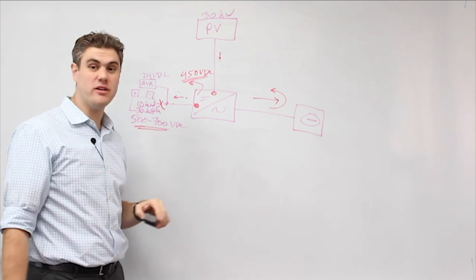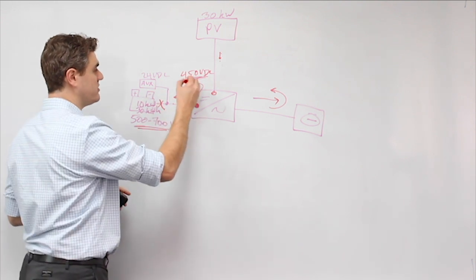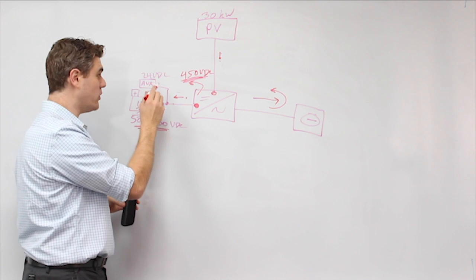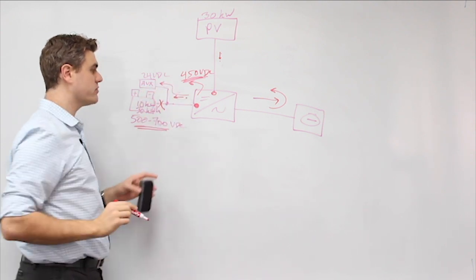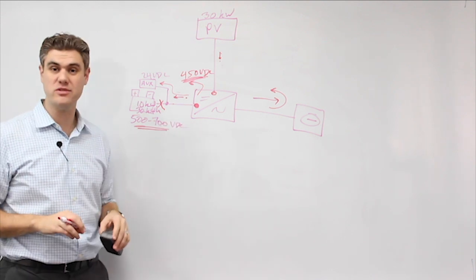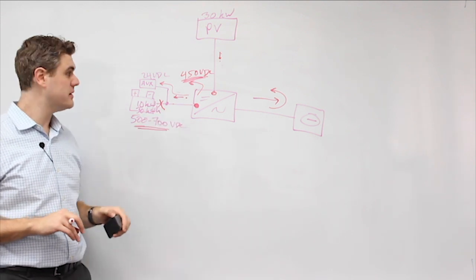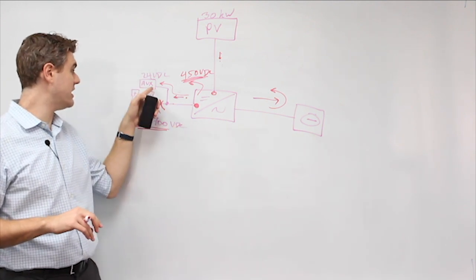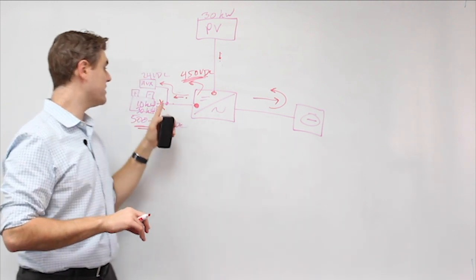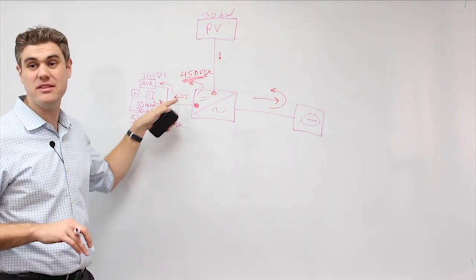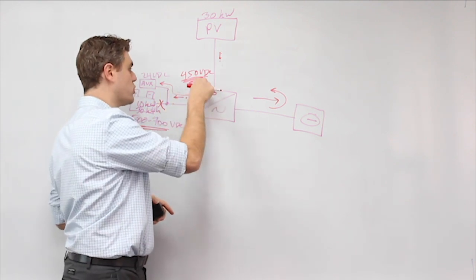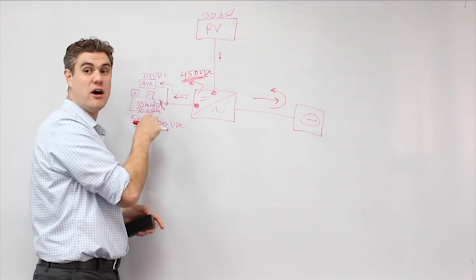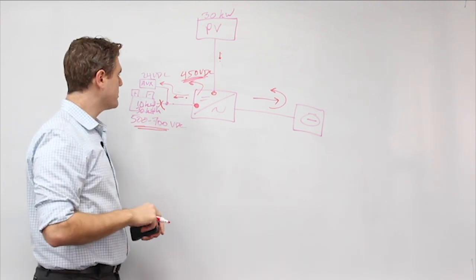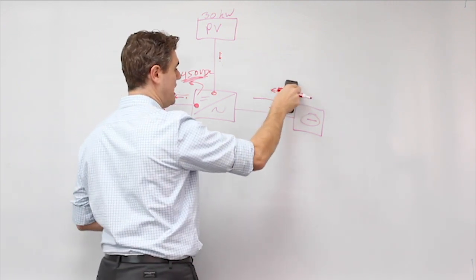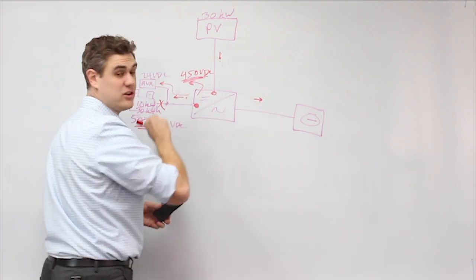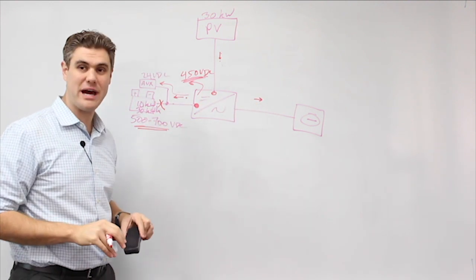It's off. But guess what's still on? These auxiliary loads, right? Just because this is at 450 volts and the aux loads are at 24 volts, the aux loads can still take energy from the port on the inverter at 450 to feed its loads and keep the battery healthy and safe. That's totally doable. And if you remember when I showed my dotted line, if these aux loads were provided by a separate circuit, the same thing can happen. There doesn't need to be this line, basically. As long as the inverter controls the voltage below the operating window of the battery, this guy shuts down, whether it has aux loads or not. So that's essentially what happens. And this guy always stays that direction and never charges. No importing into this battery.